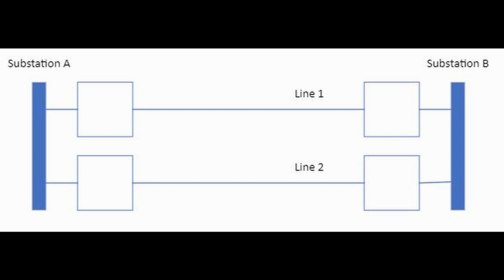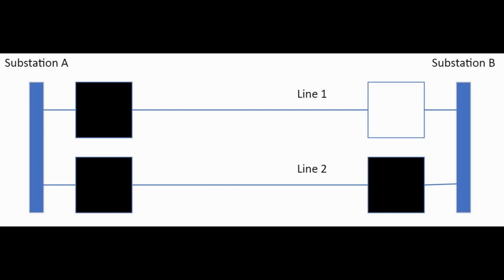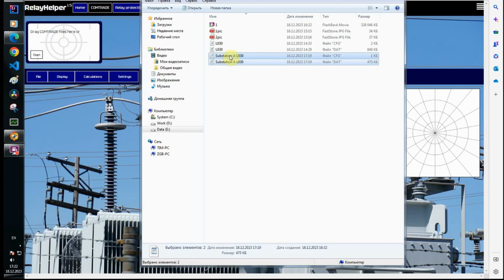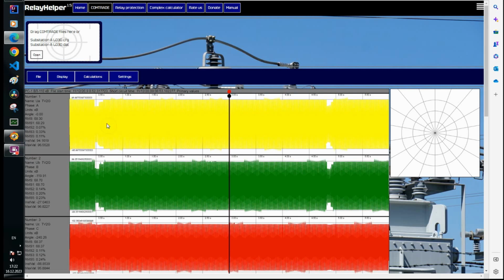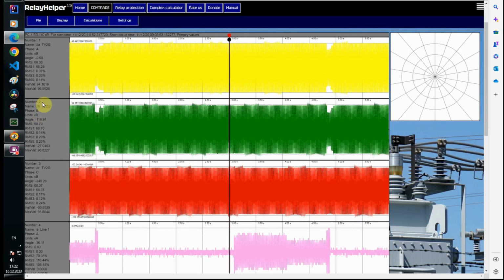the high-frequency channel. Information was received from the dispatcher about the trip of the second line with unsuccessful automatic reclose and the unilateral trip of the first line by distance protection function in the L030 device at substation A. Initially, we assumed a false operation of the device at substation A along the first line. Let's look at the recording from the general substation recorder at this substation.